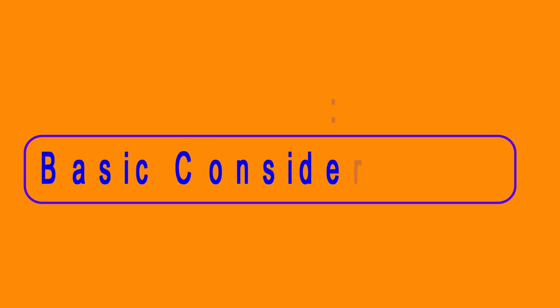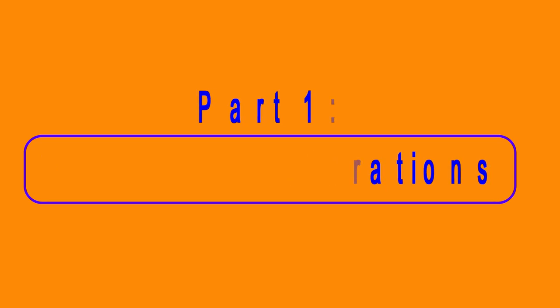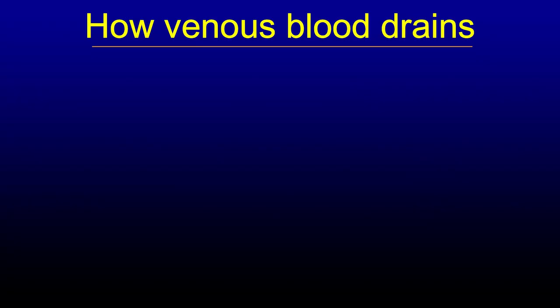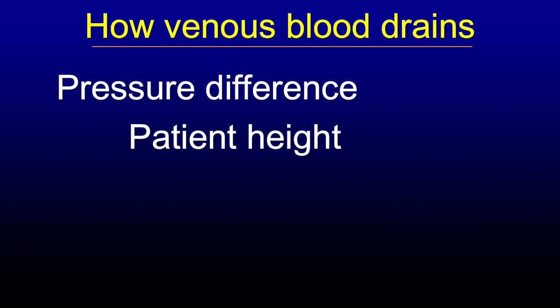The first part covers the basic considerations one has to know prior to understanding the venous drainage aspects of Cardiopulmonary Bypass. How does venous blood drain? It drains by the difference in pressure — blood always flows from a higher pressure to a lower pressure. So if the patient is at a higher level than the upper level of the blood in the venous reservoir, this difference by itself creates a flow of blood from the patient into the venous reservoir.